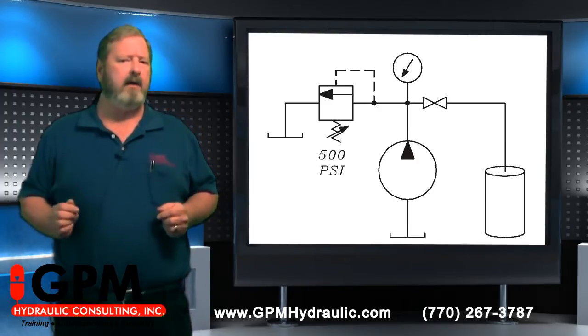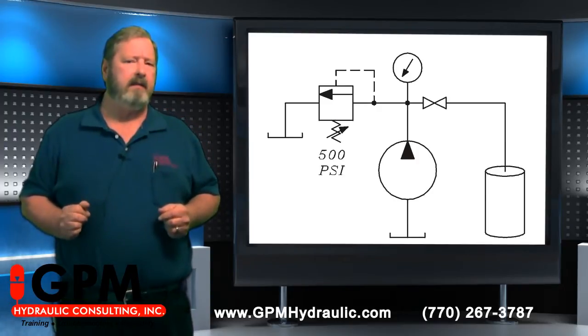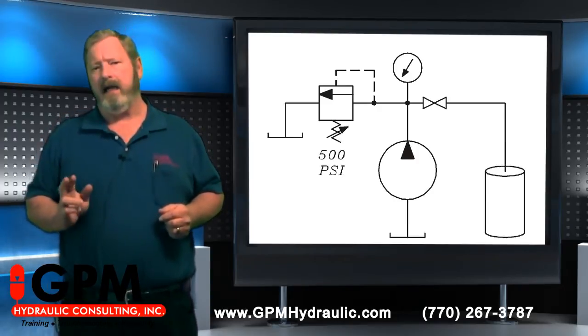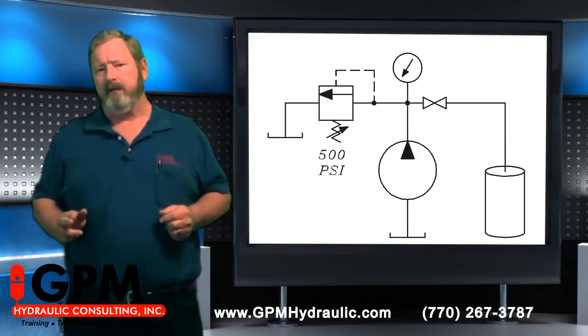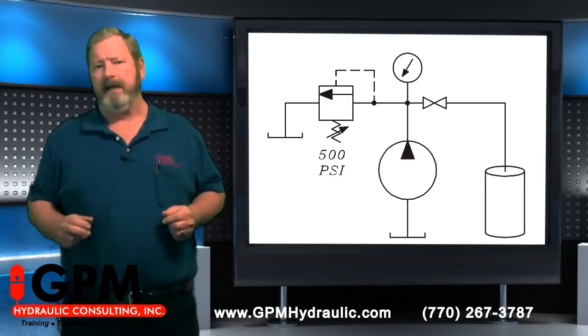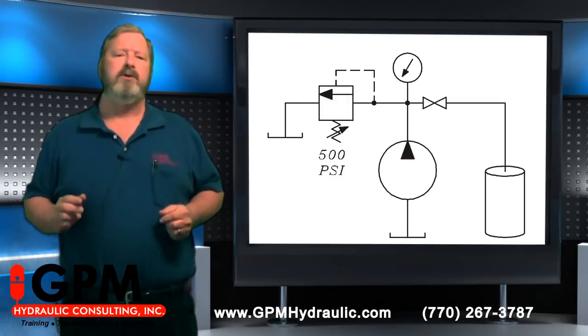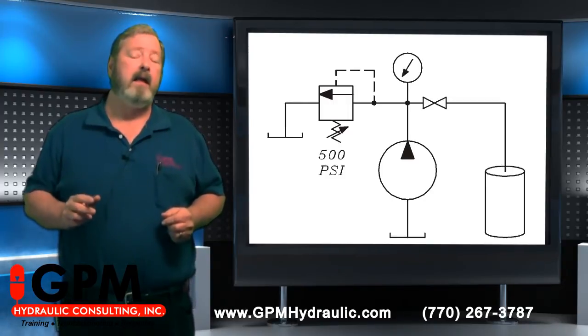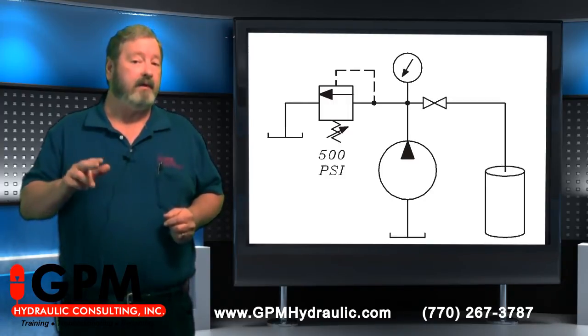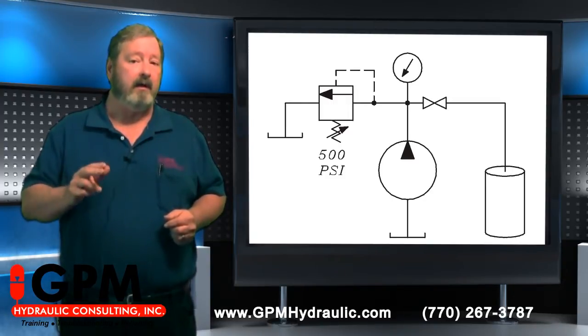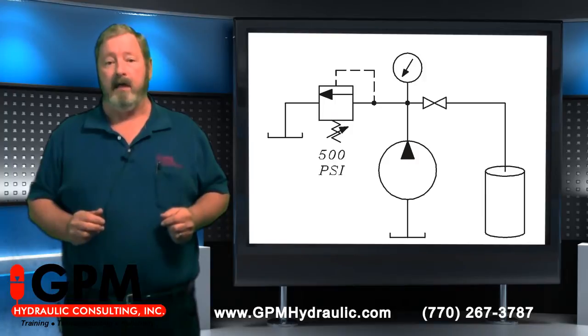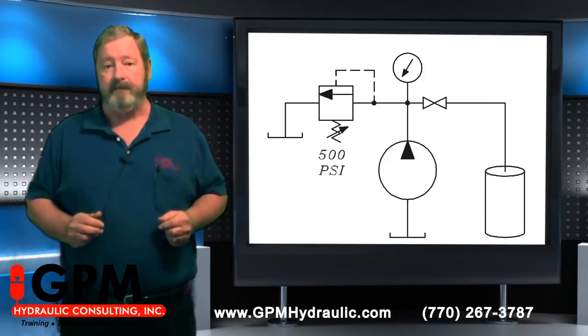So what you're reading on a gauge is not how much pressure the pump is putting out. What you're reading is the amount of resistance currently being overcome in the machine.